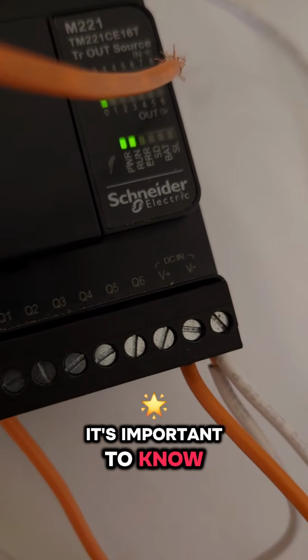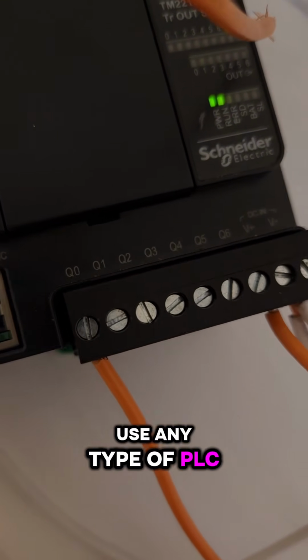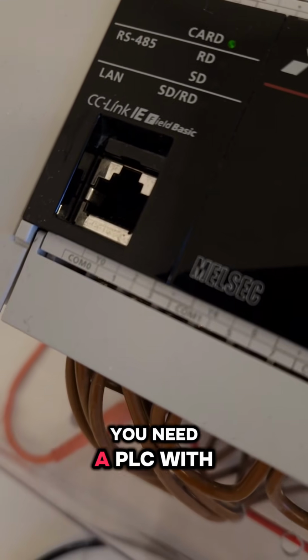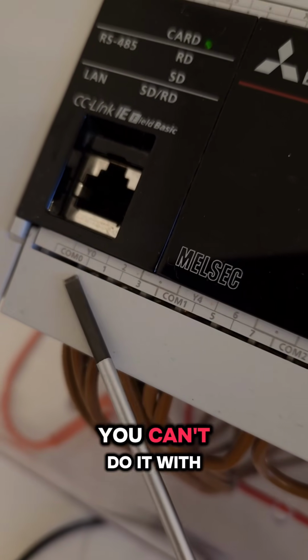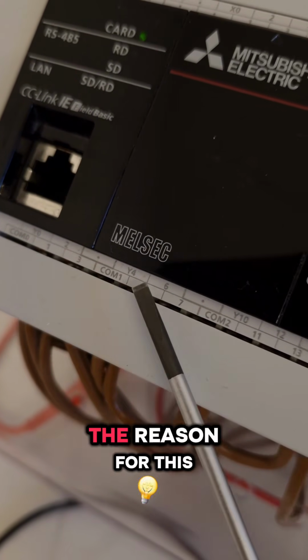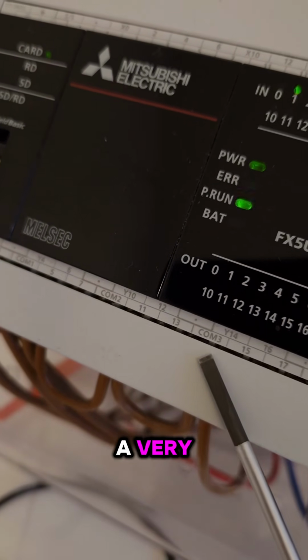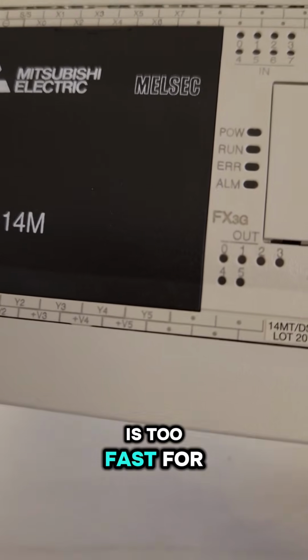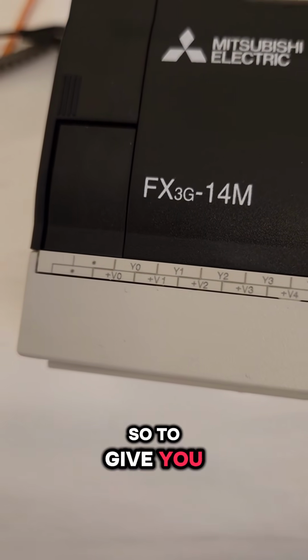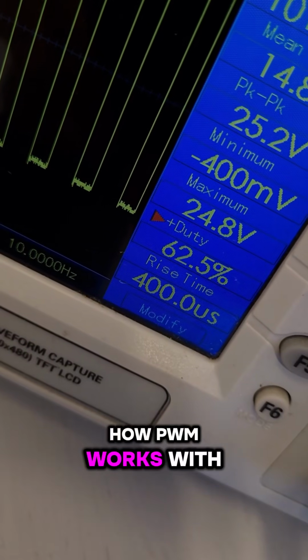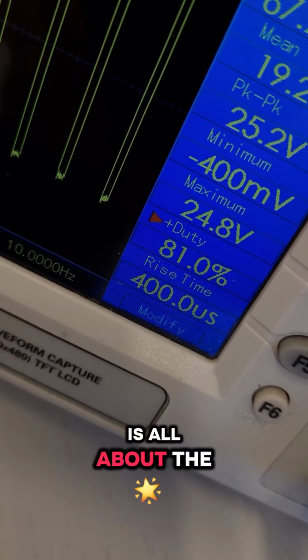It's important to know that you can't just use any type of PLC to do pulse width modulation. You need a PLC with transistor outputs. You can't do it with relay outputs. The reason for this is because you're switching at a very, very high frequency, which is too fast for relay outputs.